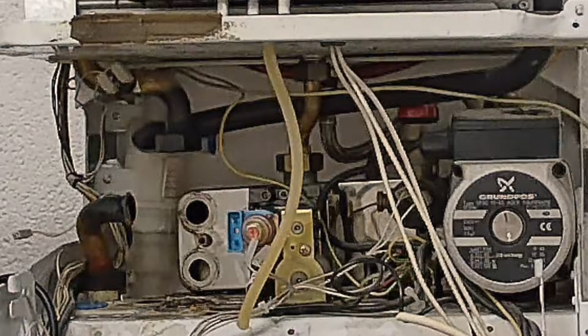Let's get the gas valve out now. First thing I'm going to do with the gas valve is remove these two wires, and this tube here, which vents off into the combustion chamber. Again, there's a screw underneath, but I don't want to undo that screw first. So, I'm going to get the nut on the bottom, which is a 30mm, and the nut at the top, which is a 24.